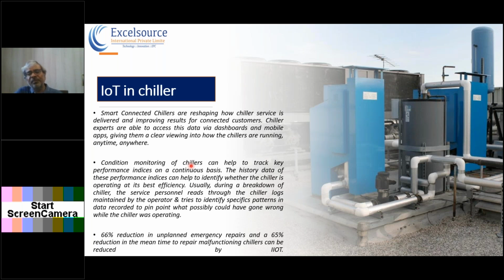This is the implementation of IoT installations in chillers. The latest chillers, as everybody has seen, come with good sensors, and analytics is given by the chiller manufacturer itself. That is an advancement, and IoT is being implemented by the new generation chillers. So if we don't have a new generation chiller, how can it be done? We can install temperature transmitters and pressure transmitters on the condenser and evaporator side, and monitor the pressure and temperature across the condenser and evaporator.